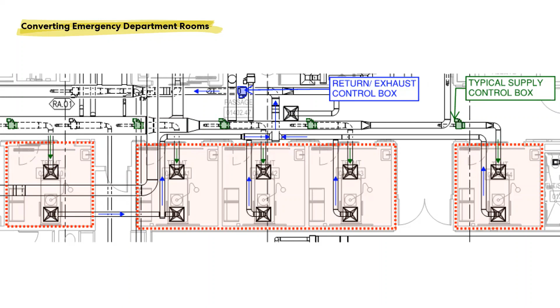The hospital at Rush is supplied air throughout the building by 12 central air handling units that are headered together on the 9th floor. Combining all of the air handling units into one massive distribution system allows the ability to take a whole riser and switch it over to exhaust as opposed to return to the building. If we look up at the upper right-hand corner where the star and the brackets are, if you imagine the northeast corner of the plan in red that we were looking at on the previous slide, we can see that we can take one whole riser and convert that to exhaust as opposed to return. This is achieved by having a dedicated return system on each of the return risers.